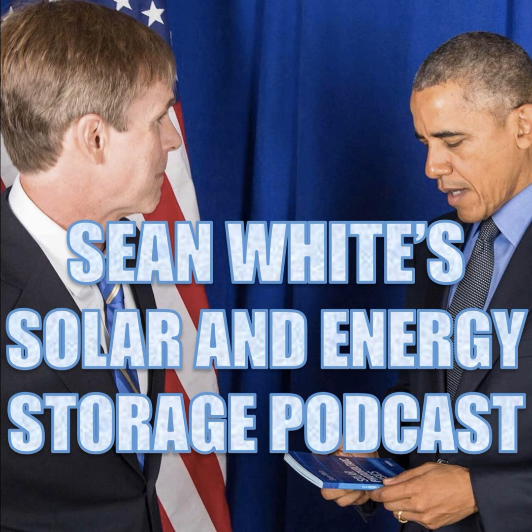So lead acid batteries, it's healthy to go up to 100%. If you don't go up to 100% every day or two, depending on who you talk to, it's bad for the batteries—it causes lead sulfate crystals on the battery cells. One of the ways to get rid of those lead sulfate crystals is to do an equalization charge. That's a controlled overcharge, the highest charge you will see on a lead acid battery.